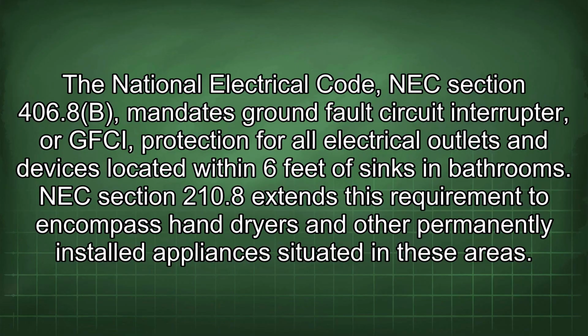The National Electrical Code, NEC Section 406.8(B), mandates ground fault circuit interrupter, or GFCI, protection for all electrical outlets and devices located within 6 feet of sinks in bathrooms. NEC Section 210.8 extends this requirement to encompass hand dryers and other permanently installed appliances situated in these areas.